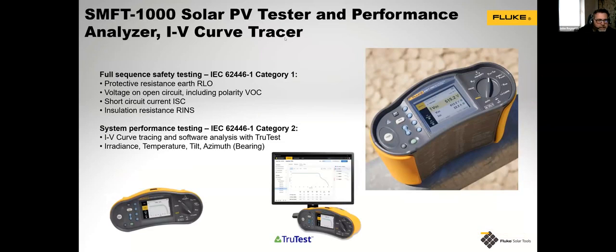Okay, so let's go into the SMFT 1000. It will give you a full sequence of safety testing as per that category, or that standard. In the category 1, providing protective resistance, earth, voltage open circuit, short circuit current, and insulation resistance.